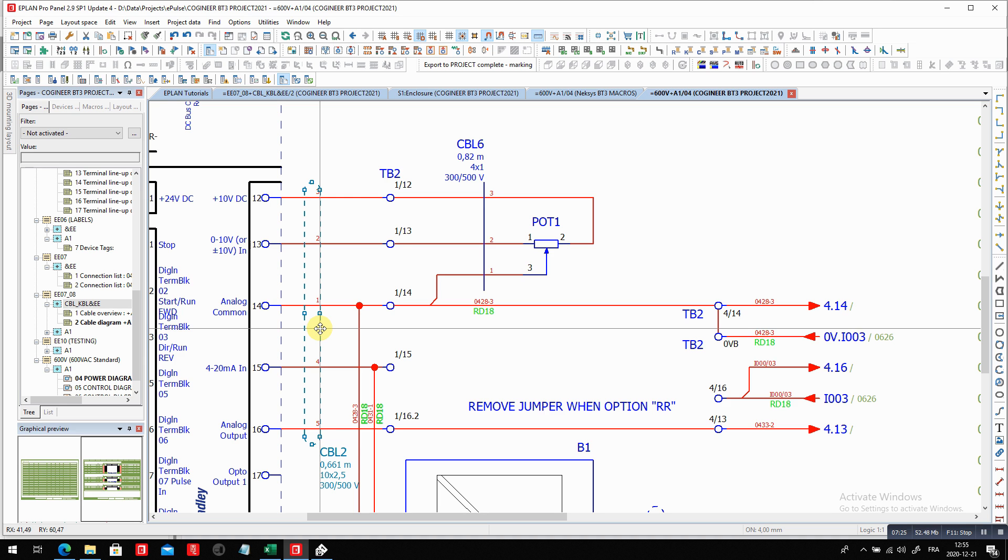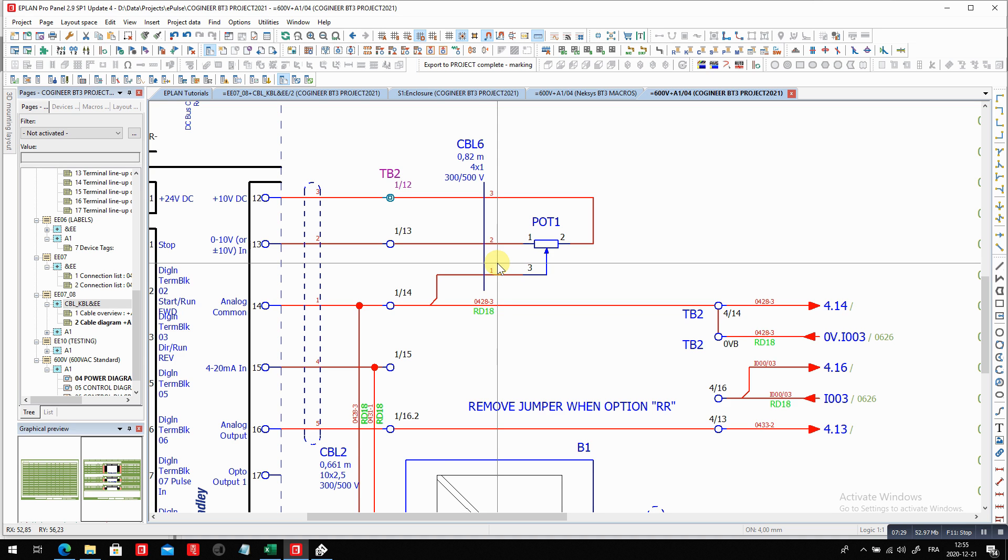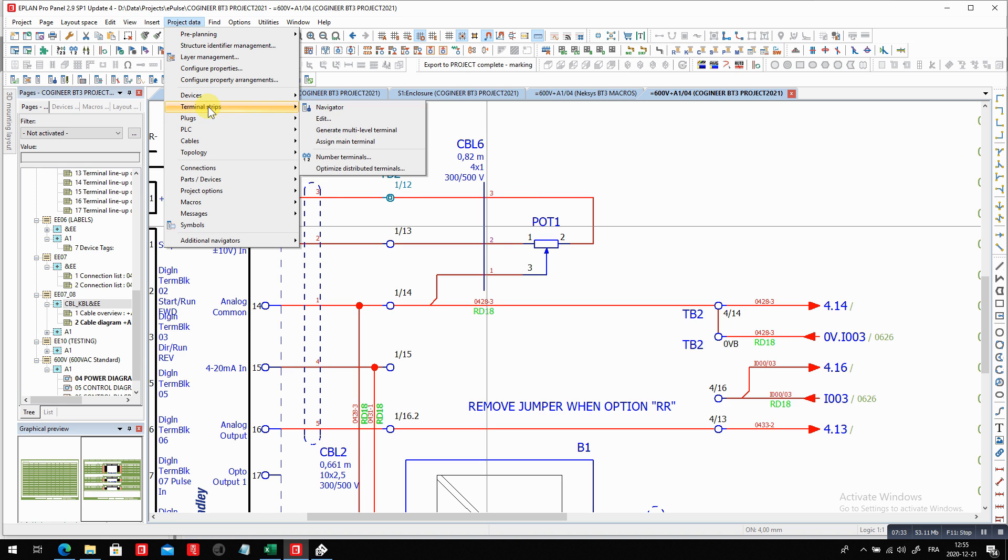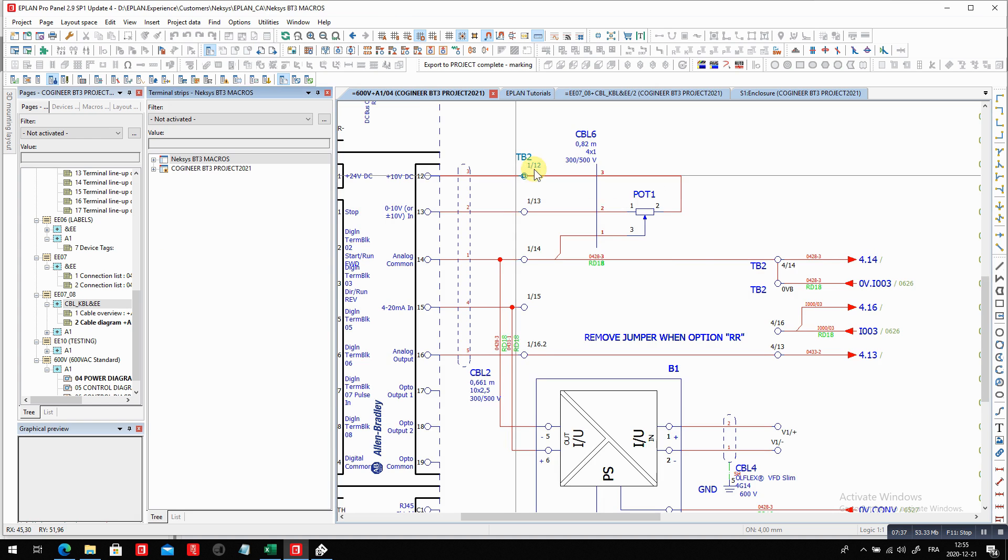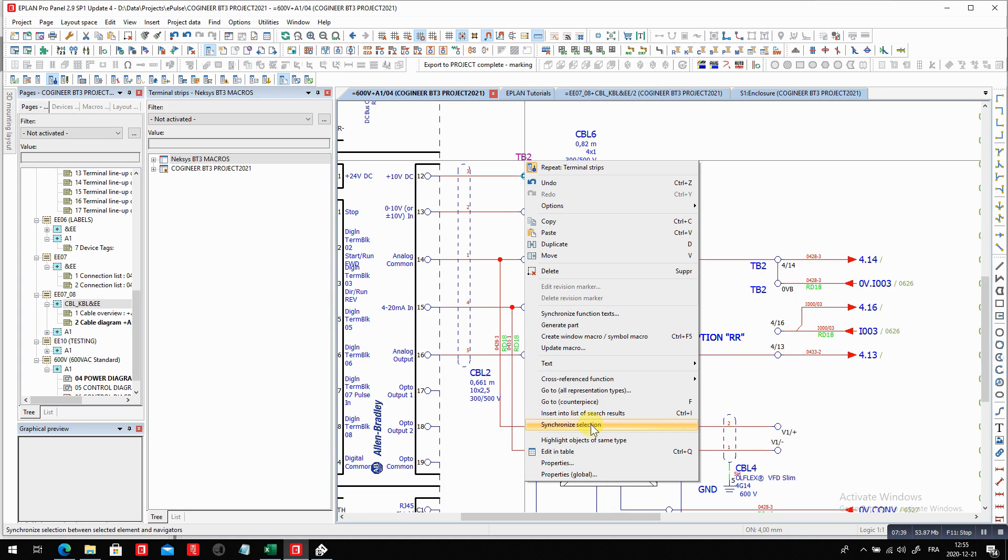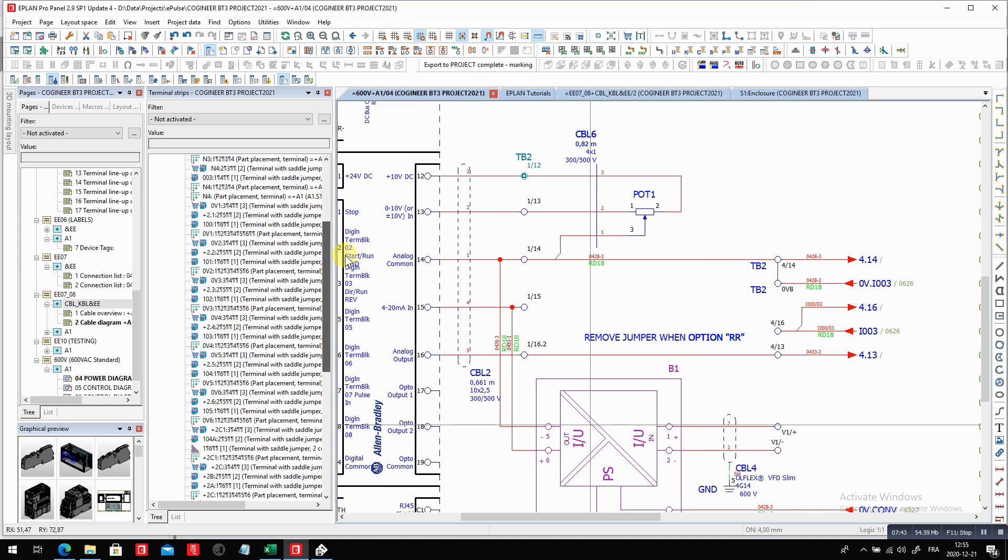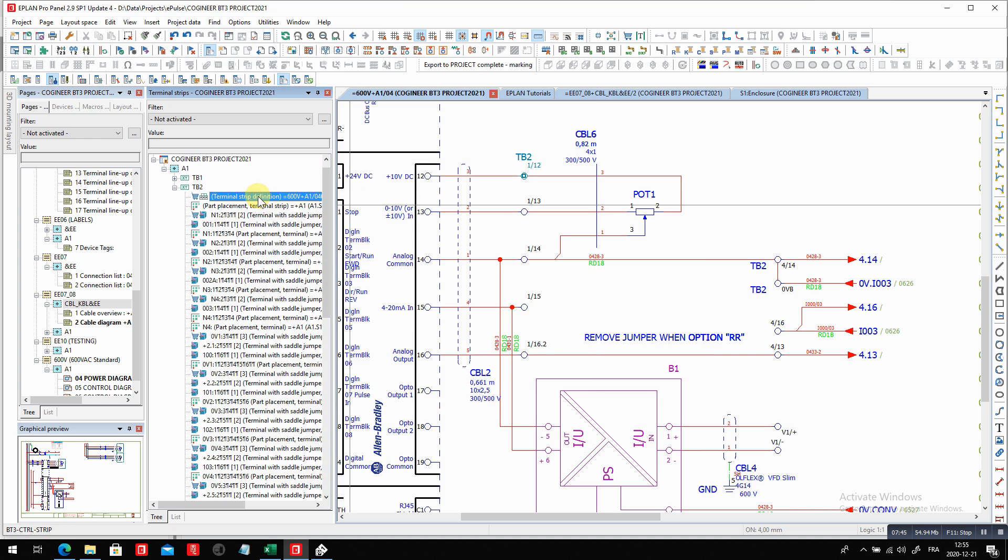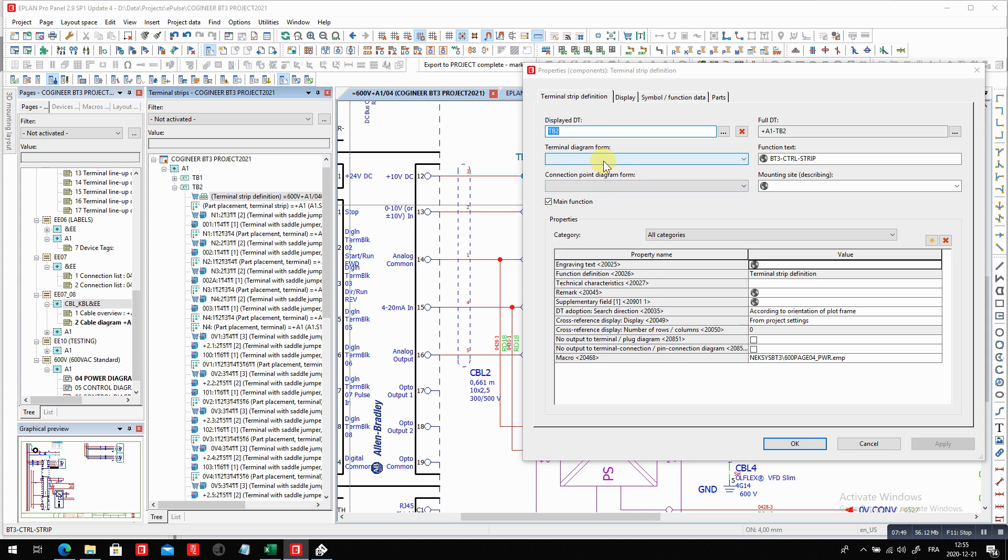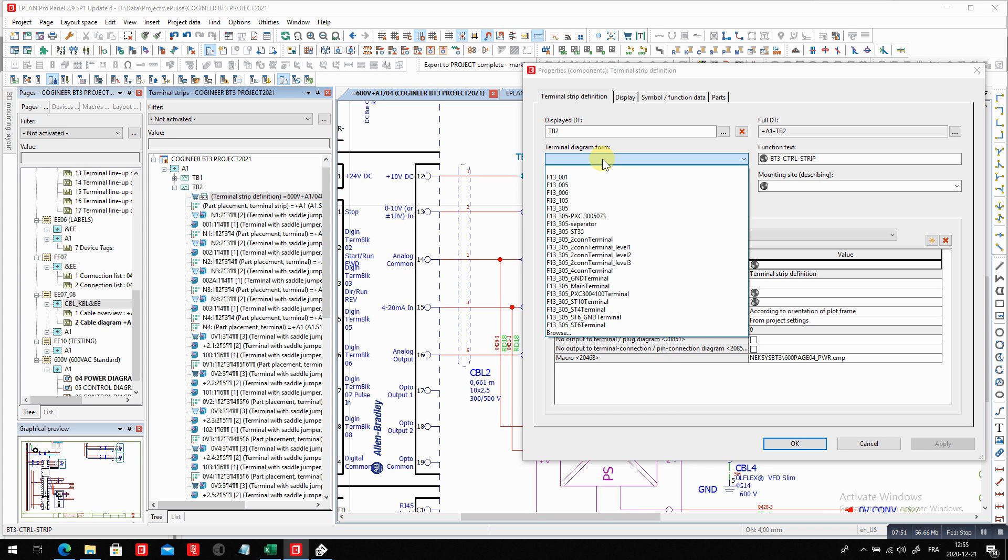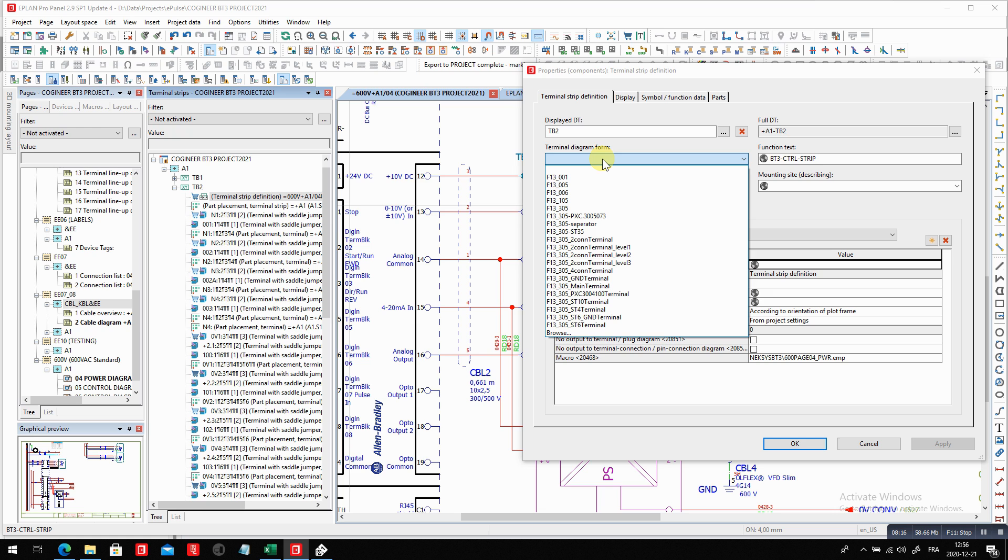Last but not least is the usage of the terminal strip and the terminal strip itself, which can serve specifically here under the navigator. When we synchronize, this is often how I look for it. So I right mouse click on a terminal and I can find it. You can see that we can define a terminal strip. And on this terminal strip for this particular one, you can choose very specific forms to be used when you generate the terminal diagram. Now, cute about this is that you can specifically choose a multi-level terminal diagram for multi-level typical terminals versus regular ones. So that would be something that you can do. Or when you know that you have two targets on most of your wires, on most of your terminals, so two wires per out or in of a terminal, you could change, you know, the report. That's really nice.